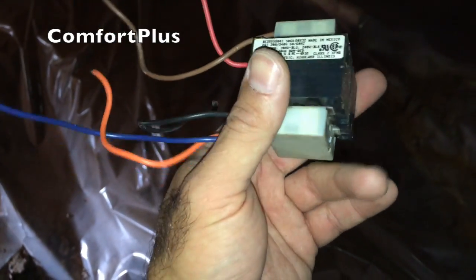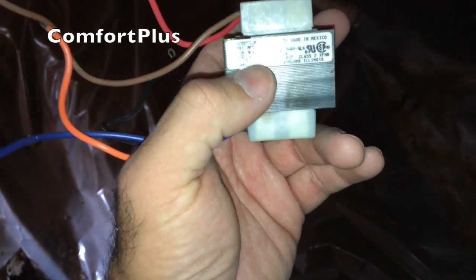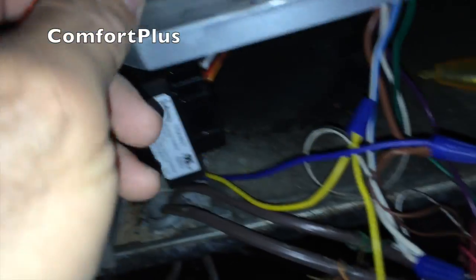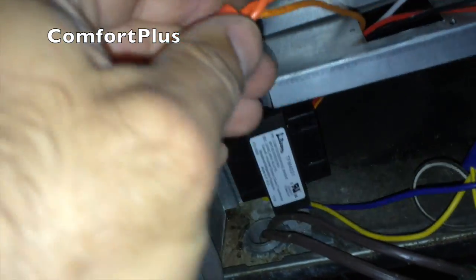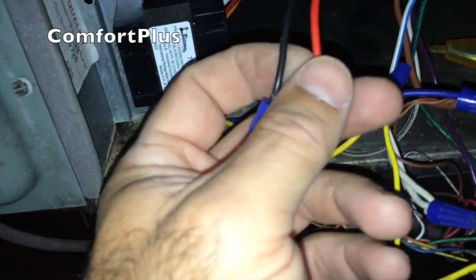Okay guys, here's the old transformer. It was of course a 24 volt, and it's a 40 VA. Here's my new one. I just mounted it down here where the optional ground lug location was. The wires will come right through this hole. This is a high voltage. I have the orange going to orange, the white going to black. That would be for 240 volt configuration. I think on this one the black is 120 volt if you use it with the white, in case you had a furnace. And then the red would be 208 volt.